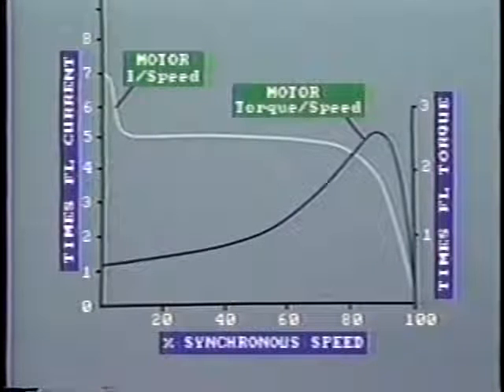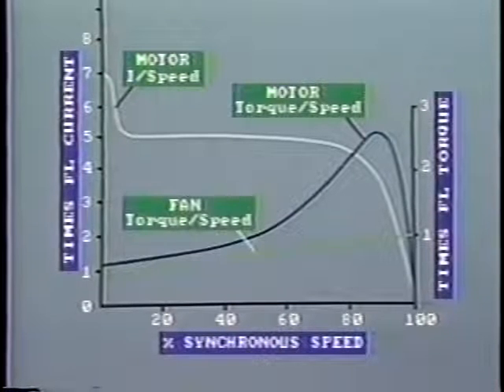Torque refers to the amount of mechanical turning force which is available to drive the fan. The torque required by the fan is indicated by this line, which is almost a straight line from zero up to operating speed. When the motor is first switched on, this small amount of excess torque is available, causing the rotor to accelerate.